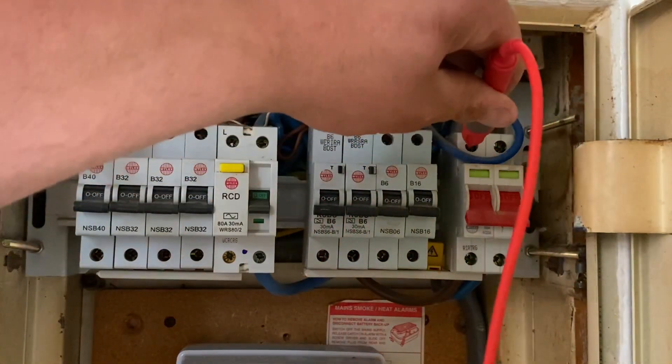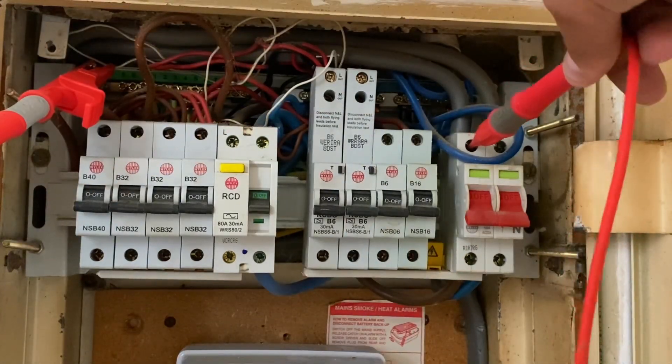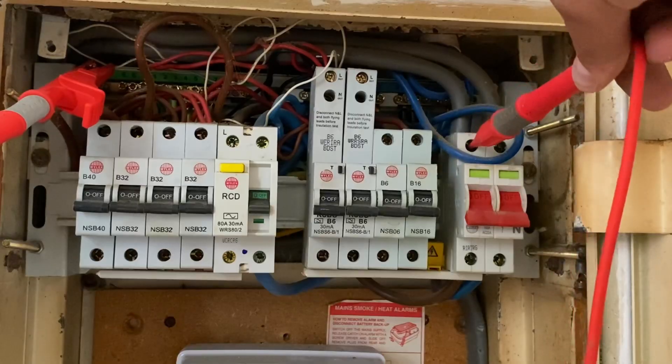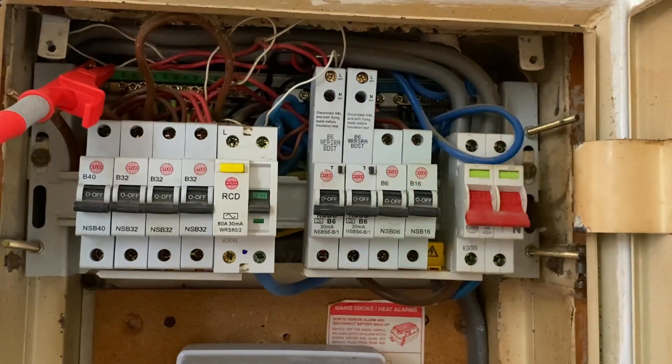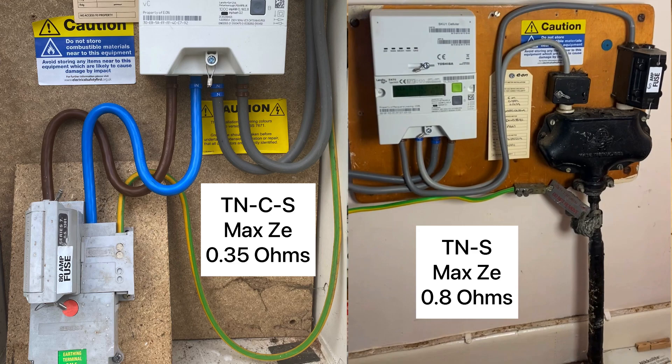I'm going to connect onto the earthing conductor and then come onto my incoming line. That has given me a reading — as you can see, quite a lot quicker than when we did the three-lead loop — of 0.23 ohms.